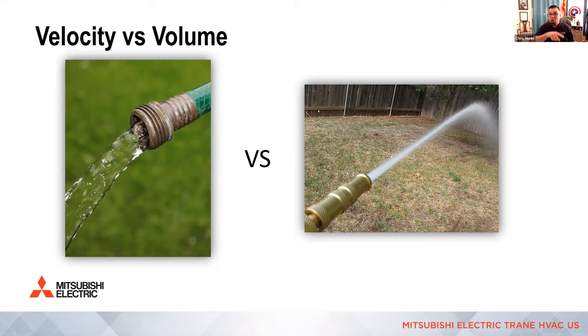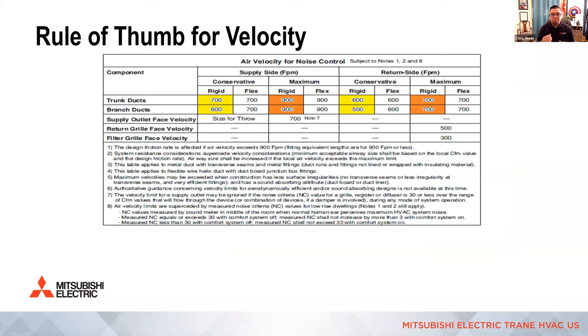So if the hose on the right is, you're trying to water something that's very delicate, it's gonna ruin it, right? It's gonna be really fast and noisy and ruin whatever you're trying to water. So the same principle applies to air, okay? There's a minimum velocity that we wanna stay above, and there's a maximum velocity that we want to stay below. Oh, that's a mouthful, I apologize. You can see that this is actually on every duct calculator. If you're using the slide rule, it's actually on the back side of the slide rule. You slide it up and all that information's right in there.